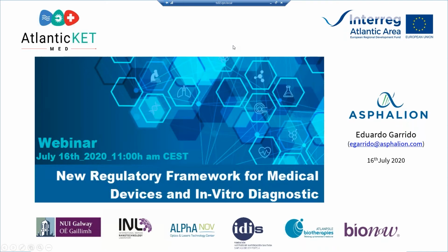There are notified bodies that are already providing this service. You should contact the notified body of your interest and see if they are doing it or not. Because right now, obviously, there haven't been many cases, because actually there are just a few, and this is something that they are starting to do now. But yeah, you should assess. You should contact your selected notified body and ask if they're doing this procedure already. Obviously, they should be designated under the regulation.